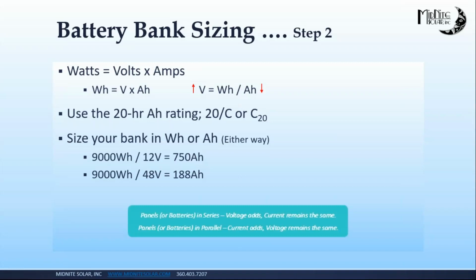And the issue with that is charging that up, and we'll talk about that in another lecture. But if you took this up to 48 volts, you're decreasing the amp hours, but it's the same amount of stored energy. That's the value of a higher voltage system, and it's because of this formula, the manipulation of this formula. So it's very important. A 750 amp hour battery, like I said, is hard to charge. So it could be a handicap in trying to charge that.